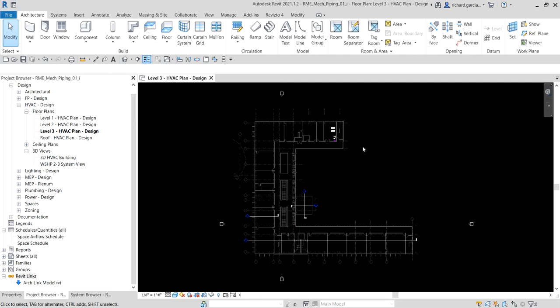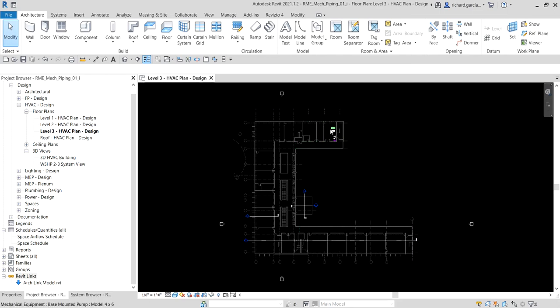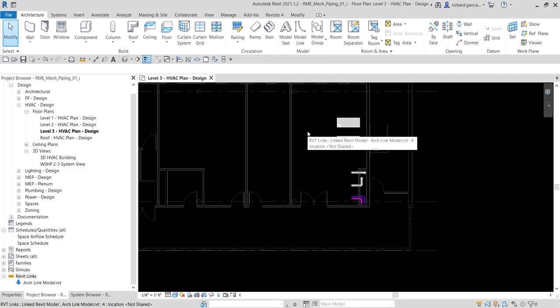We'll place a boiler on level 3 in this area here, then create the systems and piping to logically and physically connect the system components, including two base mounted pumps, additional water source heat pumps from level 1, and a cooling tower located on the roof. This system is modeled to accommodate full system flow through a boiler, using modulating valves to divert through the cooling tower during cooling mode or to bypass it during heating mode.